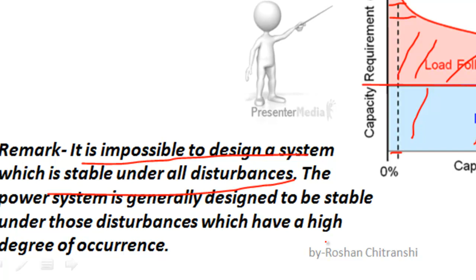Now what is the need of stability? If we do not study why it is necessary to take action about stability and why we are so worried about it, it is because stability determines the critical clearing time of the circuit breaker. It means for the equipment we are using, we need good knowledge of the circuit breaker, relay and other protecting devices, how much time they take to clear the fault, how much time they take to clear the disturbance. If the clearing time is very short, then definitely the equipment is very good.